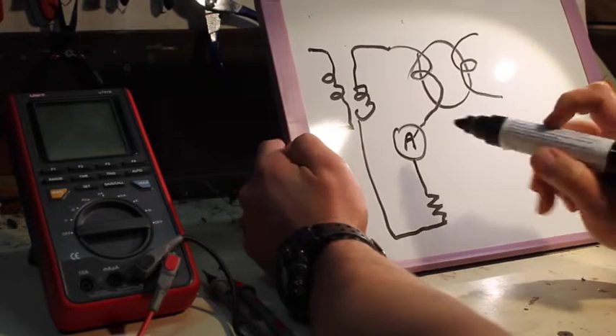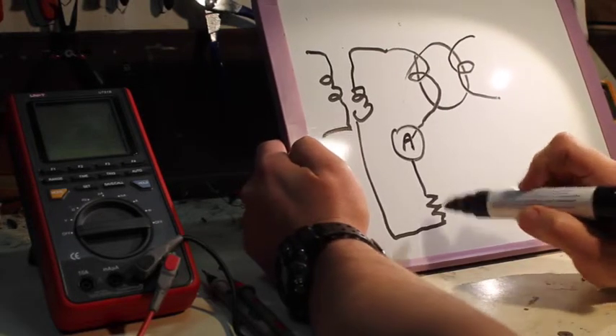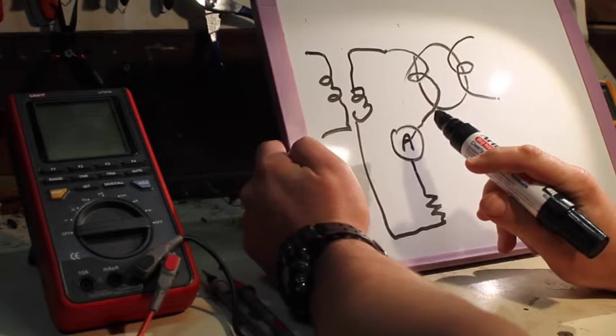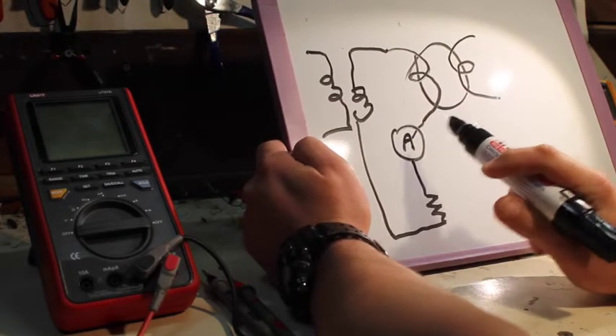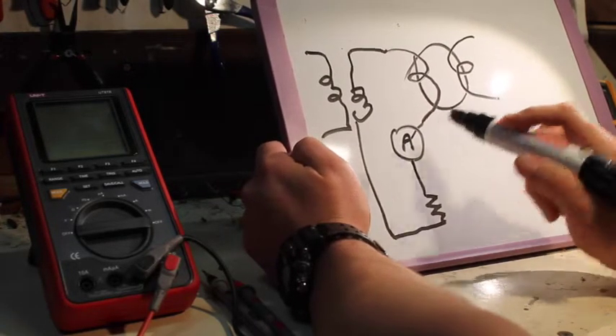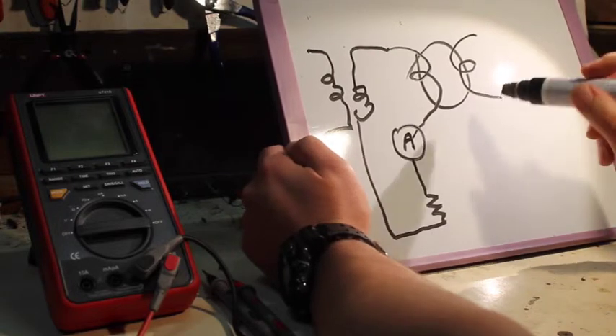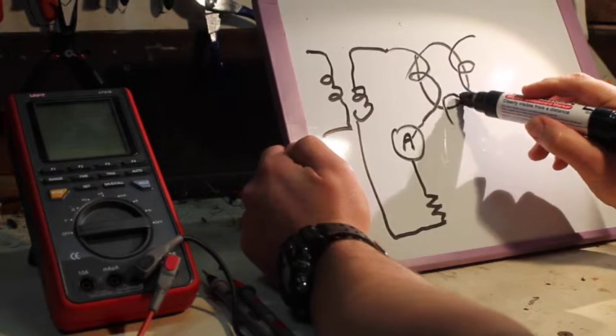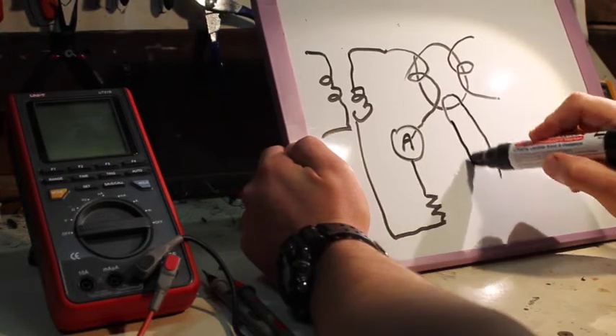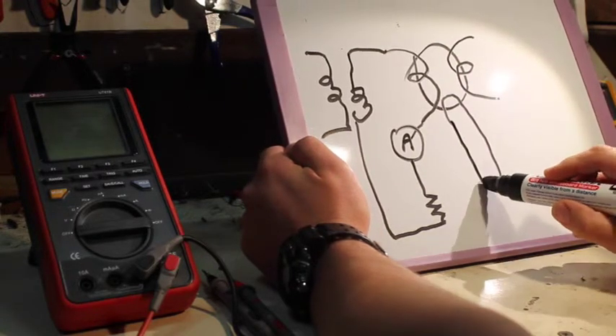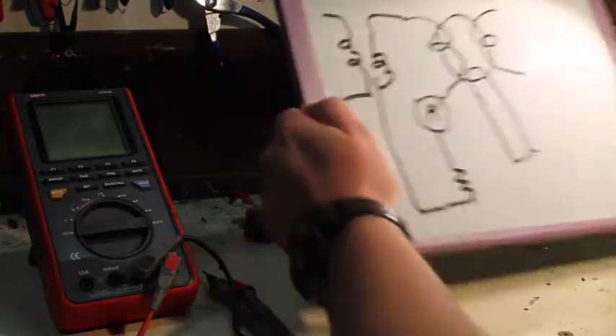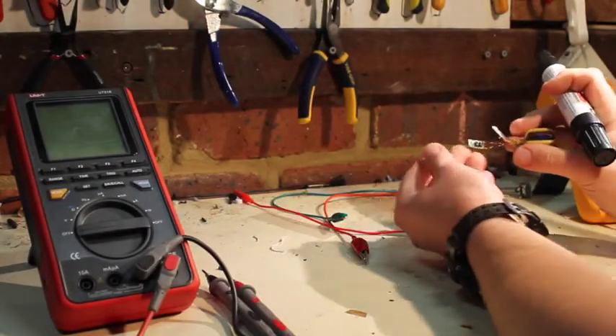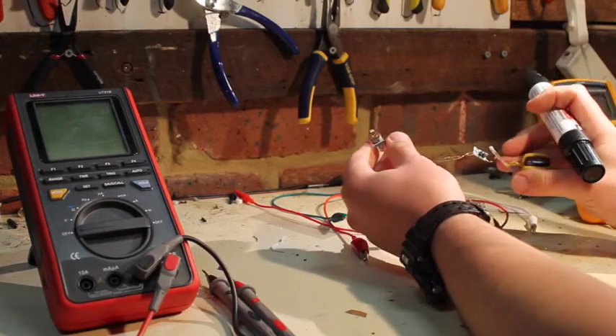What I'm thinking will happen is we'll wind up this variable resistor until we get to 30 milliamps. This RCD is designed to trip out at 30 milliamps, so we'll measure if it does in fact do that. What should happen is because it's imbalanced it should induce voltage on that extra coil and that will go through to this electronics here and cause it to trip.